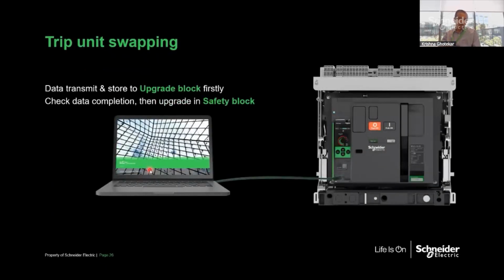Trip unit changing. Today we don't allow, for example, if you have ordered an 800 amp breaker with MicroLogic 2A of MTZ Active, and you have ordered 1250 with 5E, and now because of a design change you want to change the trip unit between them. Today with NT NW, since it is very delicate in terms of the pin installation, we don't allow it, and it's not easy for installation. Here we have made the installation much easier. So if you have to swap the trip unit between, let's say, this breaker and that breaker, from 2 to 5 and 5 to 2, you can do it by yourself. We have made it much more rigid for the changing of a trip unit.